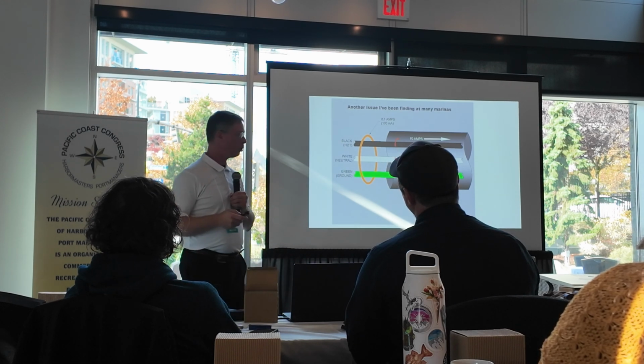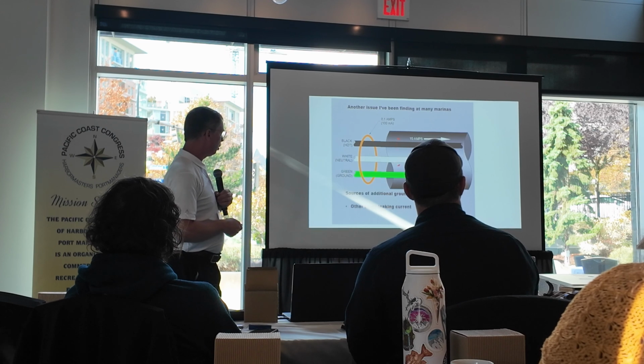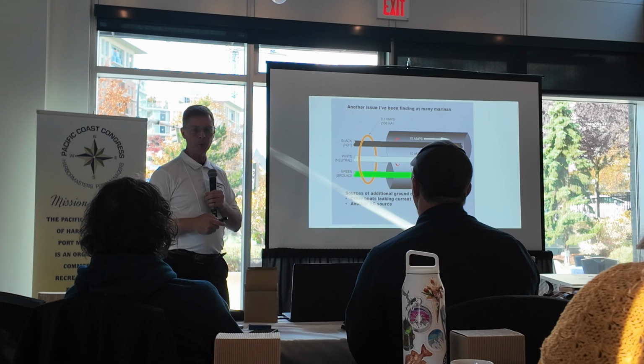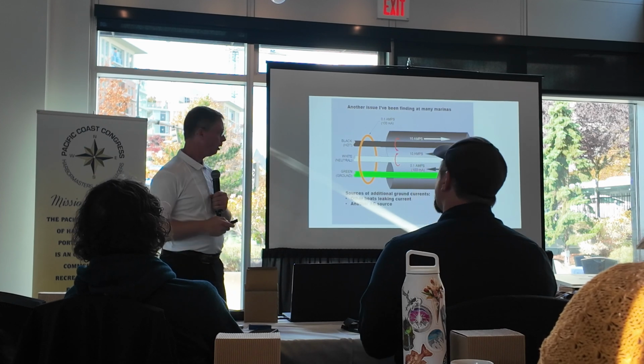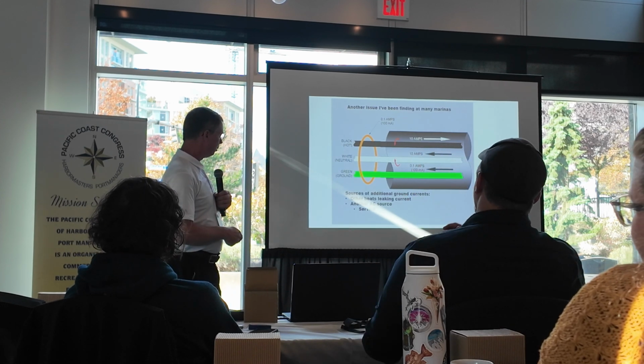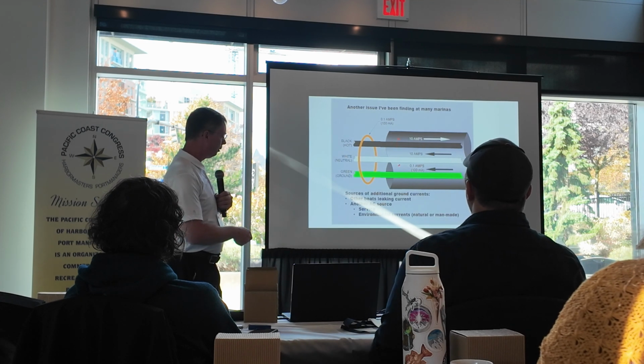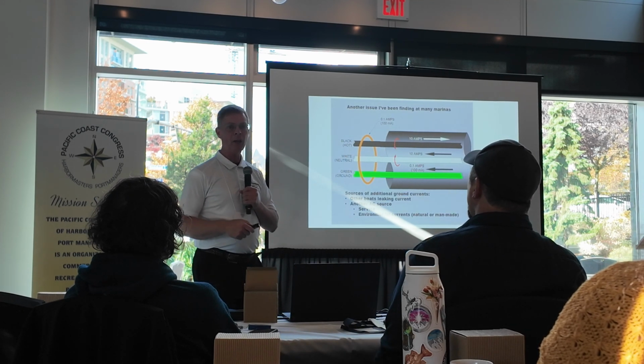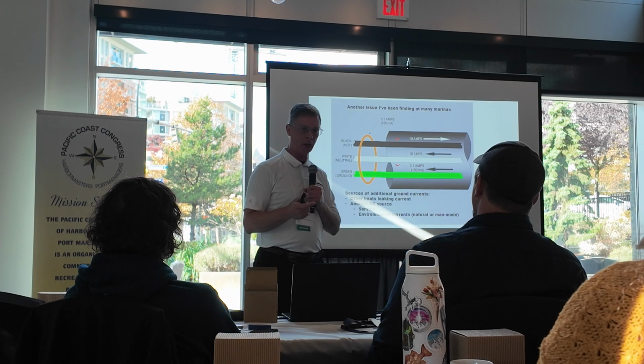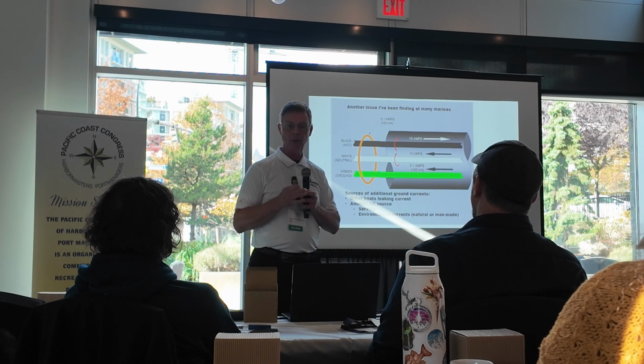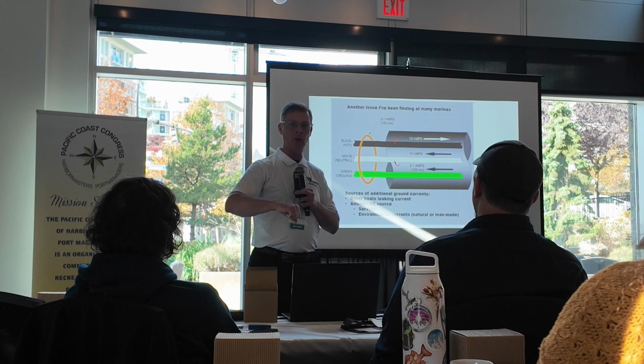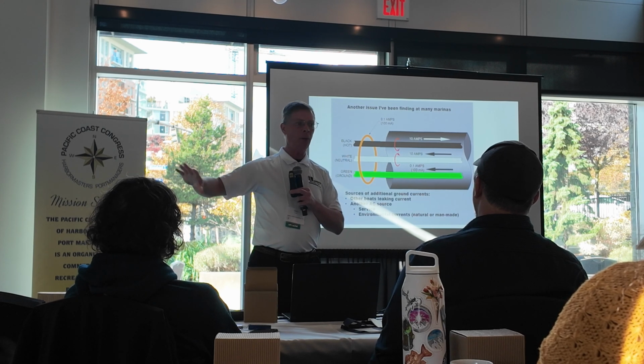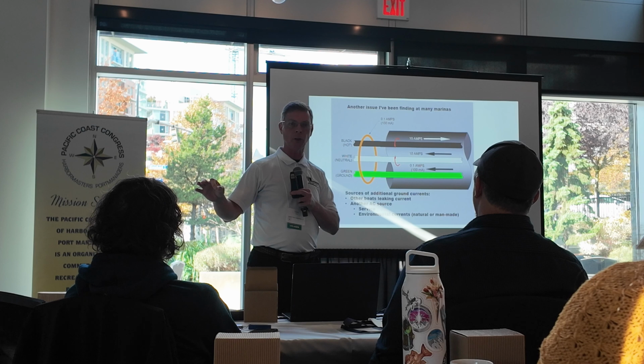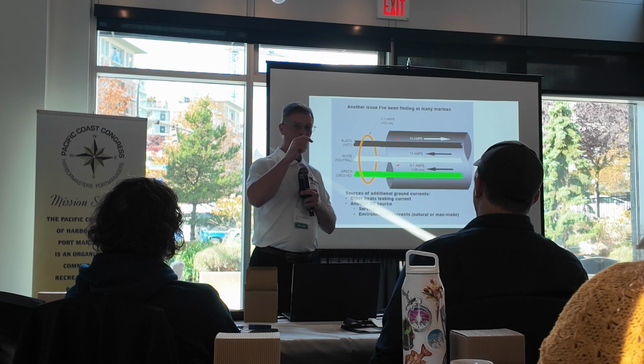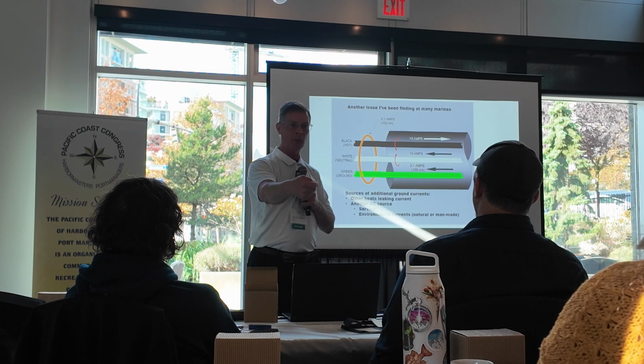But there are also situations where the source of currents could be from other boats, but also could be another AC source. I've seen where some solar panels were creating some leakage current. Also, the service, but also there could be natural and man-made currents. I've had a marina that had 2,000 milliamps on the ground current, on the grounding wire. 2,000 milliamps. We shut the main breaker off. No power on. We unplugged every single boat. 2,000 milliamps of leakage current. Had the utility come out and take the primary off the transformer. 2,000 milliamps on the ground wire.